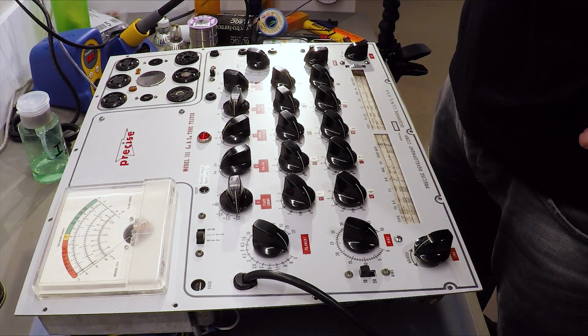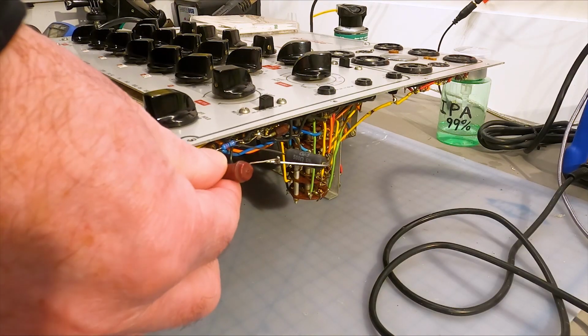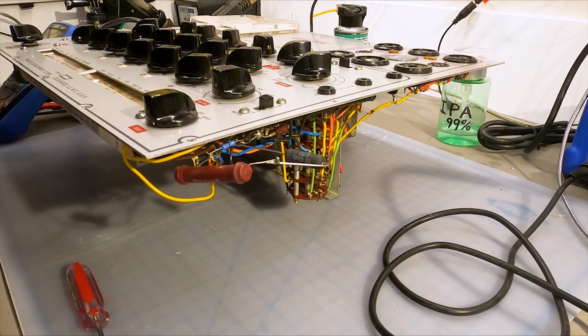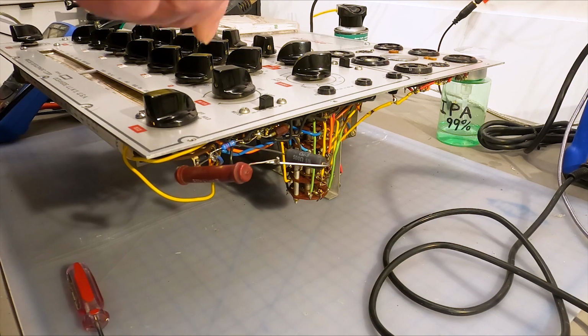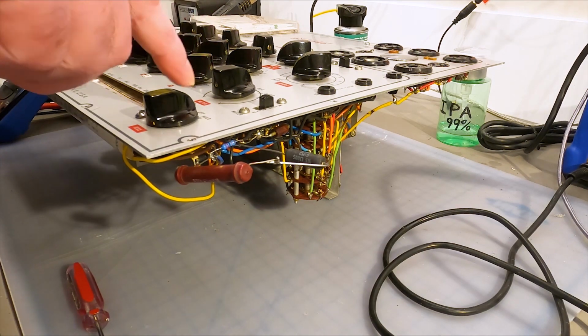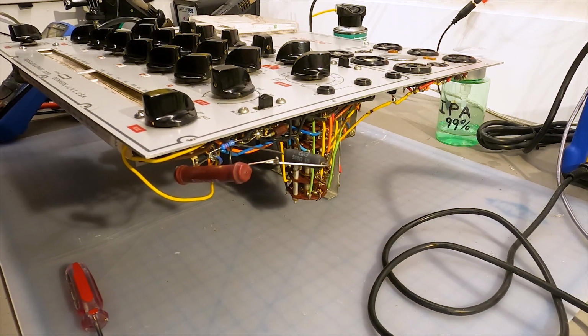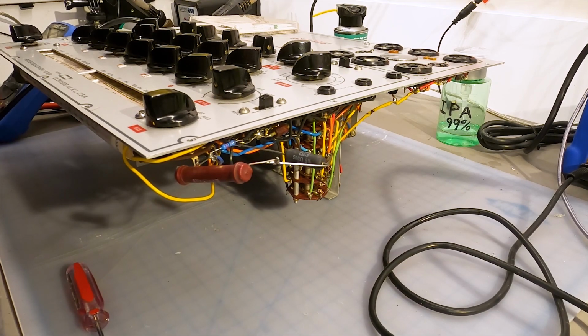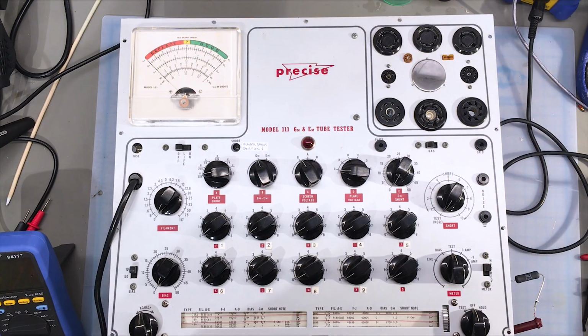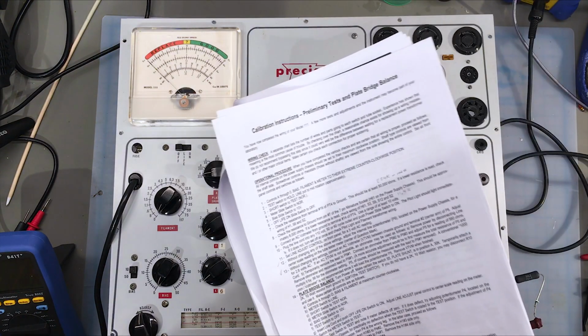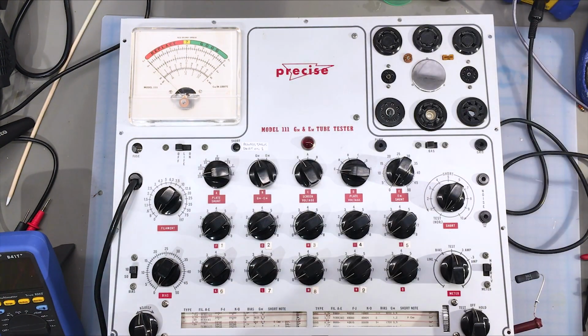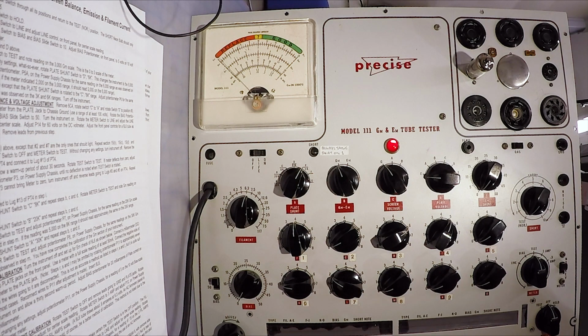And before we do that, we switch off the instrument and remove the resistor, which is attached to switch 2 between ground and position 11 on switch 2, as opposed to position 1 as erroneously described in the rewritten calibration instructions. So again, something to watch out for.